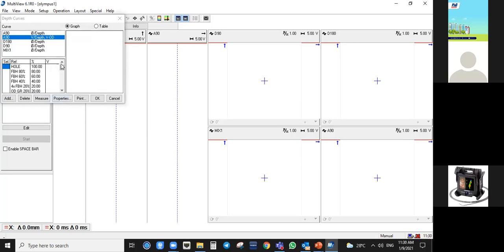Now we choose what defect we are going to detect on each channel. So you go here, A90. Remember, a while ago during the earlier slides, when you are analyzing for big defects, you use A90. Hole is not a big defect, so you unclick that one. Flat bottom holes also are not big defects. Unclick, unclick, unclick, unclick. So on A90, your big defects are OD groove 20%, your ID groove 10%, you have your big hole, you have your OD groove 40, and then your OD groove 60.